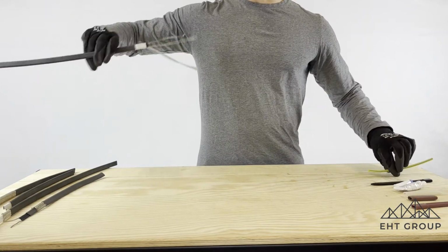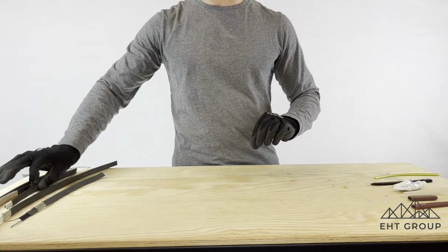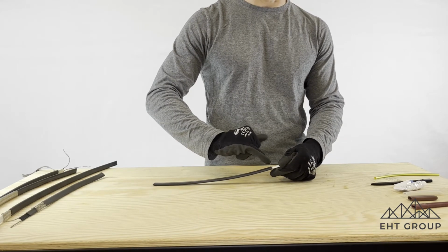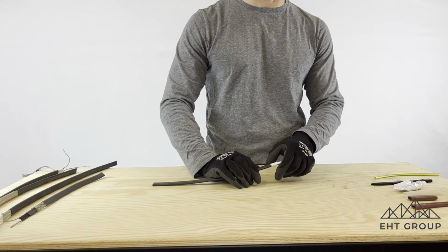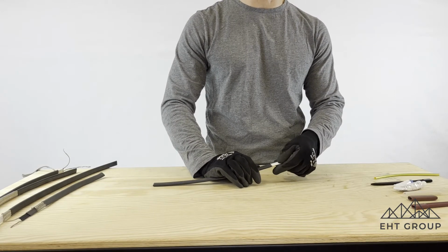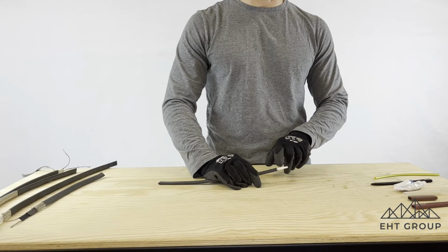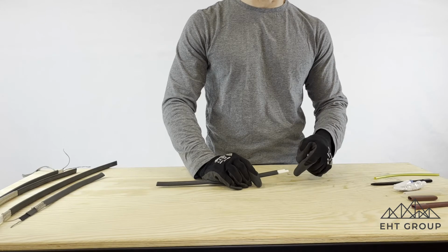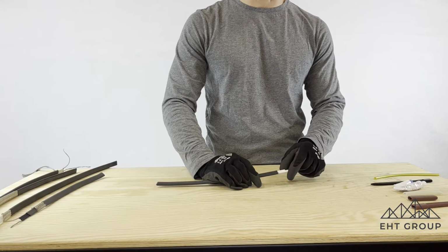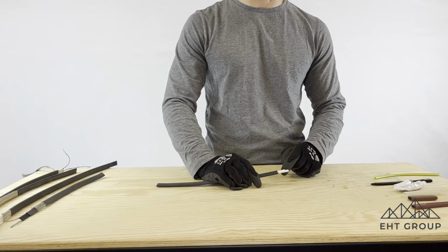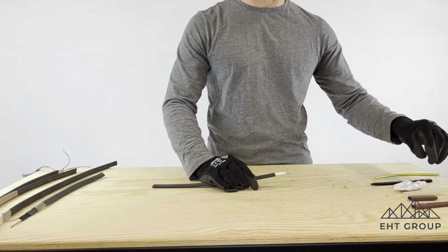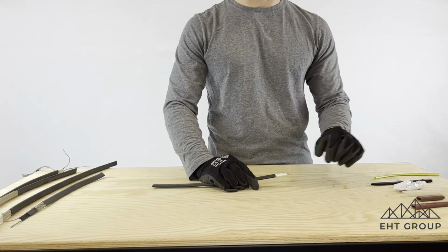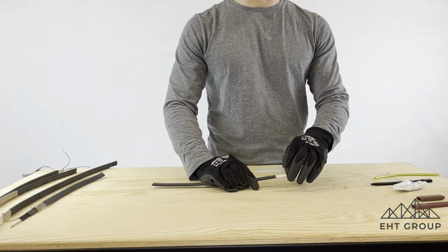The end termination is very similar. So our end termination, similar in terms of care, in terms of ensuring that we're not penetrating through that inner insulation and there's no braid that's in close contact with our bus bars. We then usually leave a space of our inner insulation, and we like to do this as we usually cut a notch in the heat trace cable, and really all this is doing is just adding distance between our two bus bars. And again, an end termination will typically, but not always, look like we'll put an end termination boot in there, and there'll be some sort of compound that'll get installed inside that boot as well.